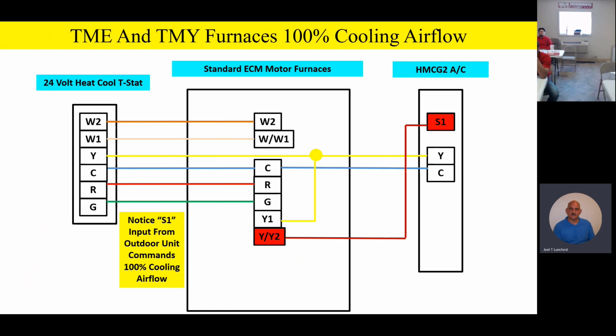Now, the compressor will modulate between 35 and 100% capacity based on what the board tells it to do, right? But the control board outside is actually taking all these temperatures on the suction line, the liquid line, the hot gas line, outdoor air temperature, all those parameters, and making intelligent decisions on what point of capacity it needs to be at. And then when it's at the appropriate point of capacity, like 60% or more, it'll generate an S1 signal and tell the indoor unit, give me full airflow.